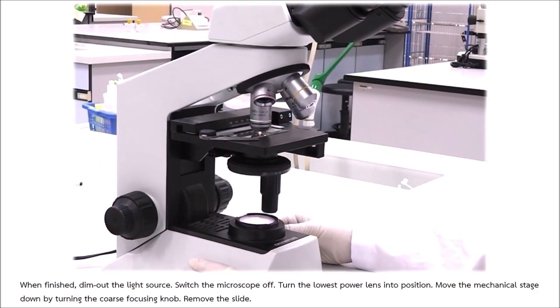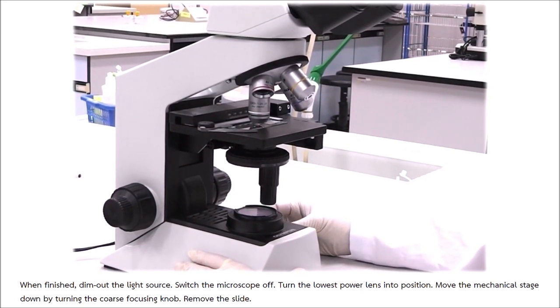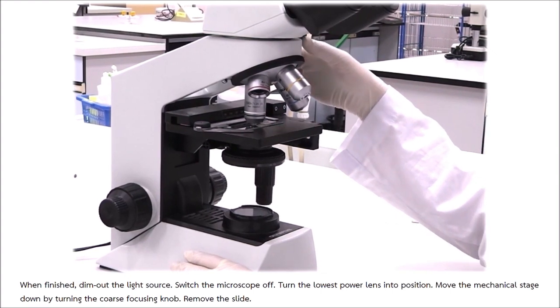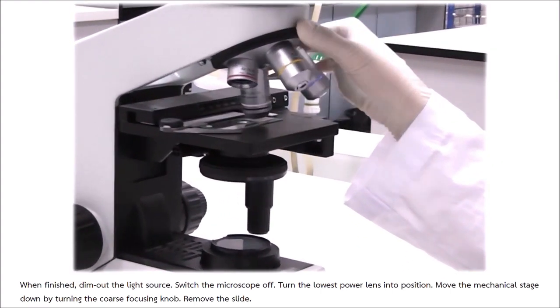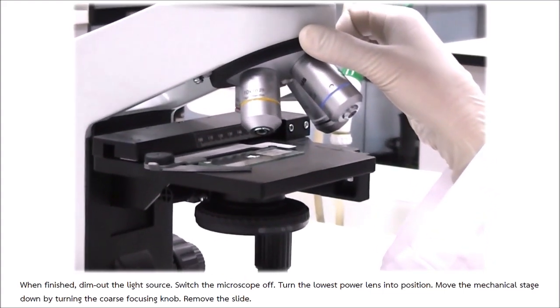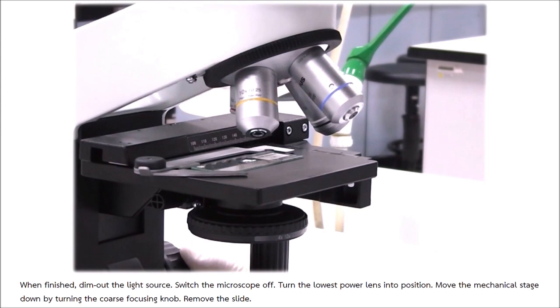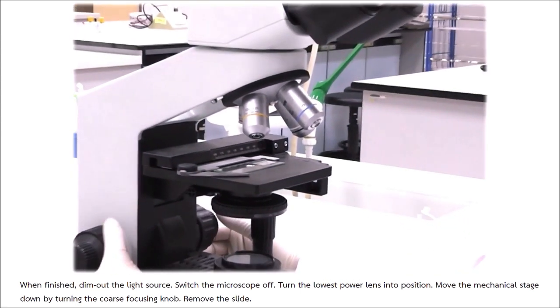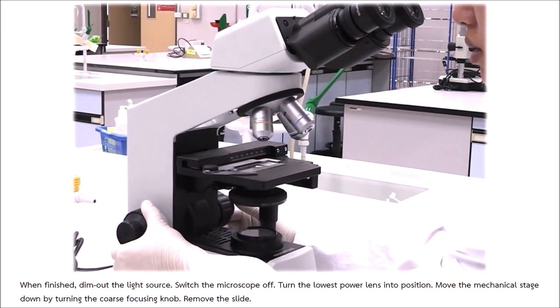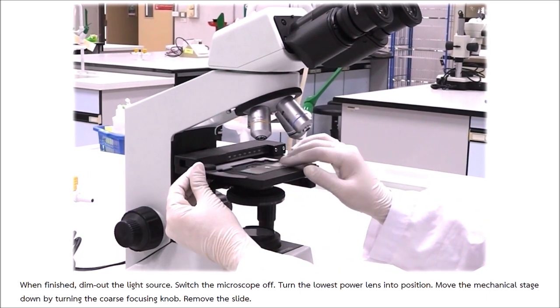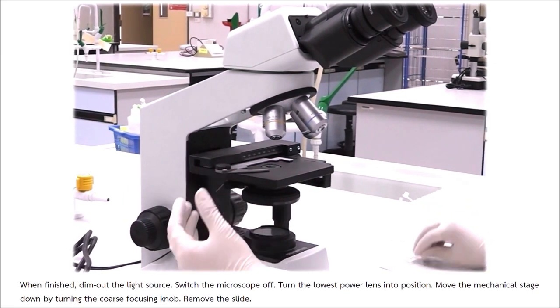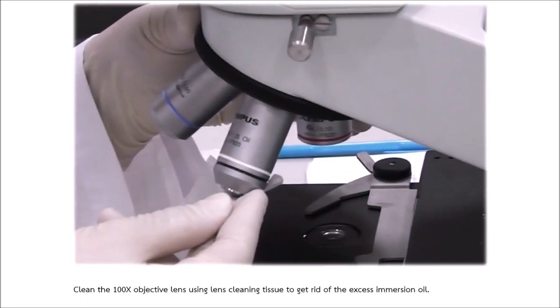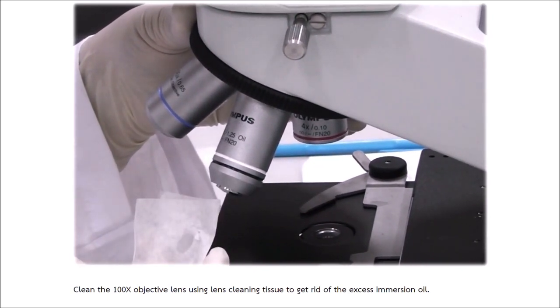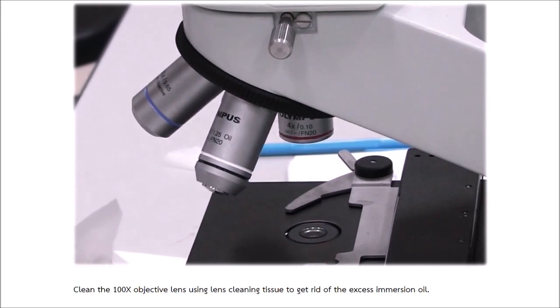When finished, dim out the light source. Switch the microscope off. Turn the lowest power lens into position. Move the mechanical stage down by turning the coarse focusing knob. Remove the slide. Clean the 100x objective lens using lens cleaning tissue to get rid of the excess immersion oil.